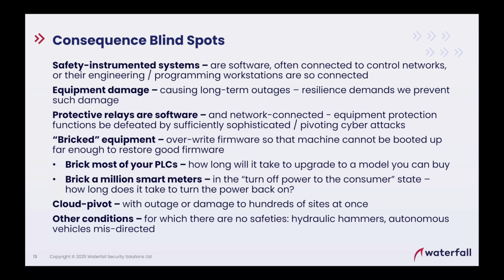What happens if most of our PLCs in a power plant or a pipeline are bricked? A lot of us have 10, 20, 30% spares because we expect these things to last 10, 15 years, and we know the vendor isn't going to be selling these things at the end of the 15 years. So we buy enough spares to tide us over when natural failure of these devices occurs over time. We don't realize that if someone comes in and bricks 80% of our PLCs, we only have 30% spares. Now what do we do?